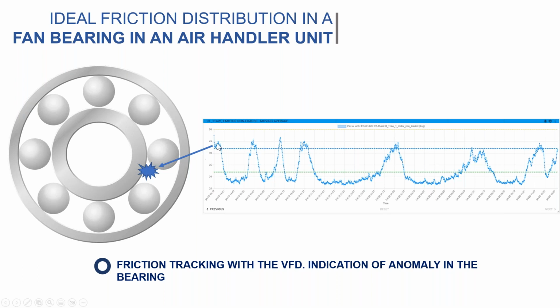So if you were to put the RPM, or if you have chillers, loads, FLA, the full load amps, and you were to plot it with this, the peaks and valleys just match. So it becomes very intuitive, very simple. That's why people are drawn towards ultrasound: the simplicity.